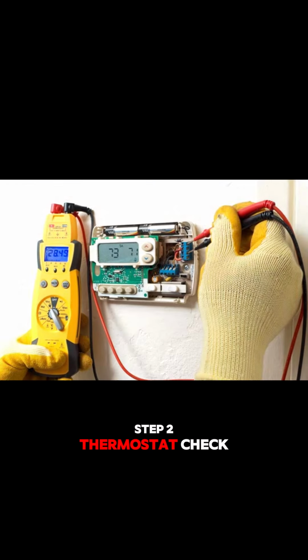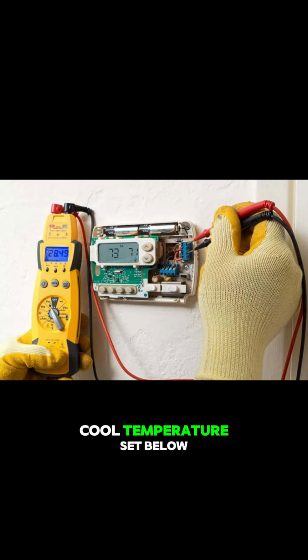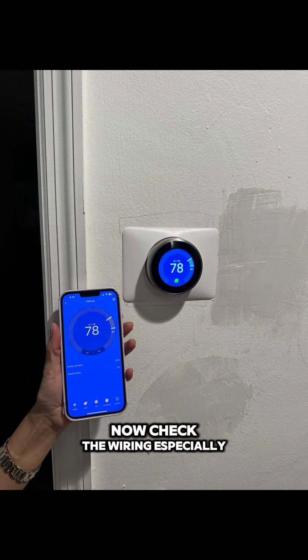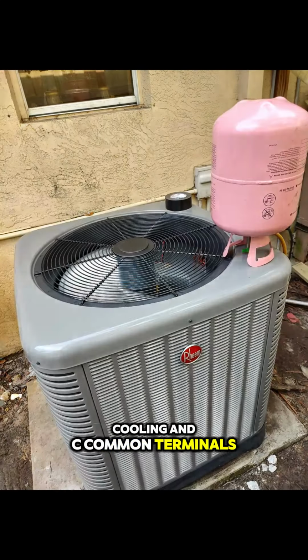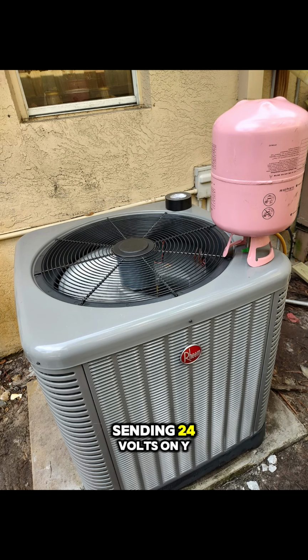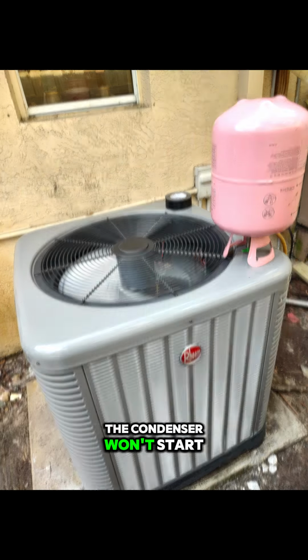Step 2. Thermostat check. Is it set to cool? Temperature set below room temp? Check the batteries if it's digital. Now check the wiring, especially the Y, cooling, and C, common terminals. If the thermostat isn't sending 24 volts on Y, the condenser won't start.